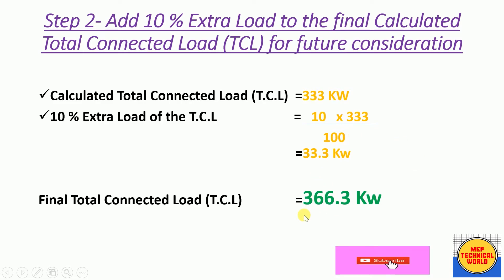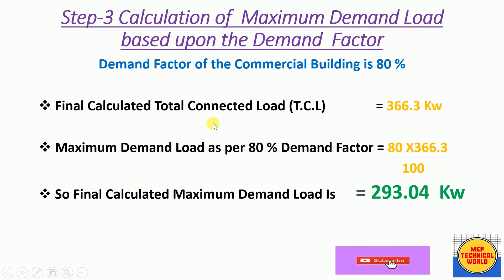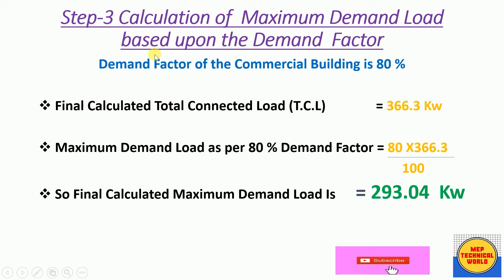In Step 3 we calculate the maximum demand load based upon the demand factor. Demand factors differ by building type: for a commercial building it is 80%, for a residential building it is 60%, and for an industrial building it is 90%. Since our hotel building is a commercial building, we will use a demand factor of 80%.